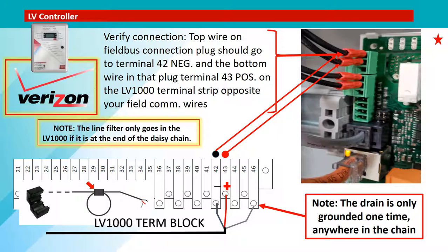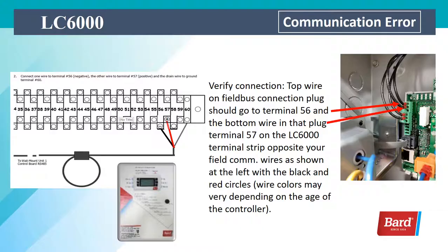The bottom wire in that plug goes to terminal 43, which is marked positive on the LV 1000 terminal strip — opposite the wires you're connecting in the field. The line filter only goes on the LV 1000 if it's at the end of the daisy chain, and the drain is only grounded one time anywhere in the chain. If you're working with an LC 6000, the top wire on the field bus connection plug should go to terminal 56 and the bottom wire to terminal 57, opposite your field communication wires as shown with the black and red circles.